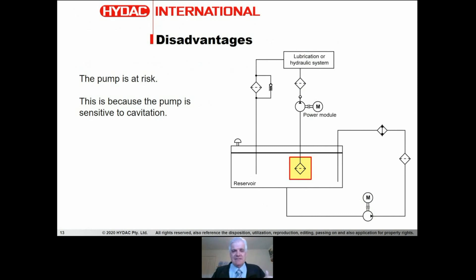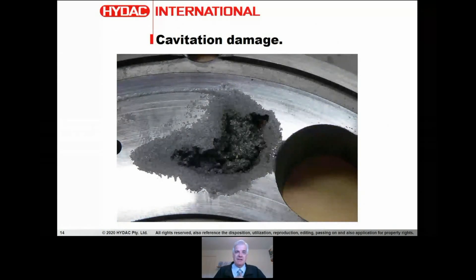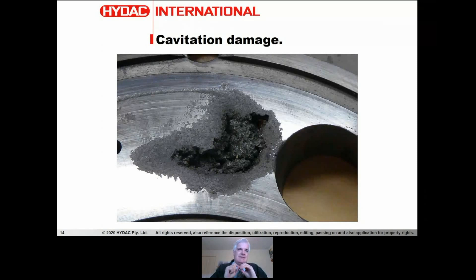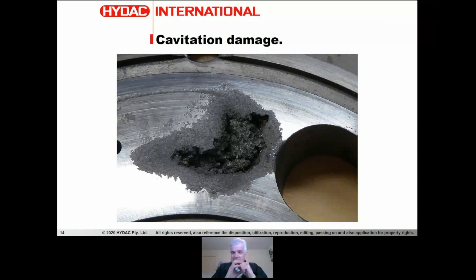The disadvantage of suction filtration is that the pump can be at risk because it's very sensitive to cavitation. Cavitation is incredibly damaging. Here's a photo of a lens plate from a large pump showing a very deep cavity created by cavitation. In a ten-second explanation: a partial vacuum develops inside the pump, creating vapor bubbles within the fluid. Those bubbles expand and then snap back as the pump creates pressure, which is incredibly damaging.